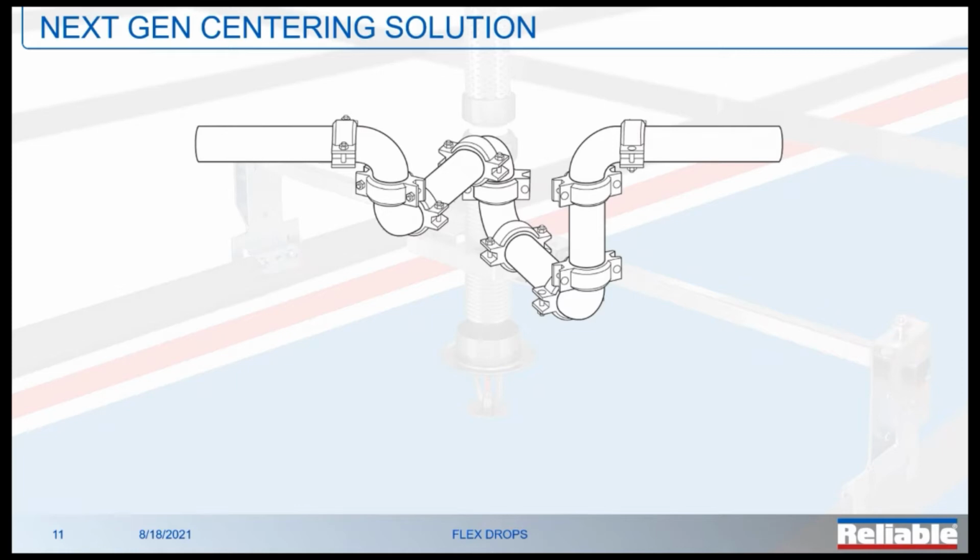But it also came to me that this option that you see here, this 690 10 coupling option to cross a seismic joint, which still can be used today, can be replaced by something else. And what is that something else? It's a braided flexible hose that allows movement in different directions.